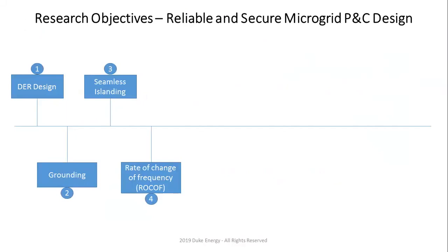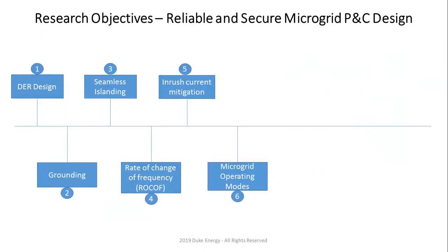Then there's going to be a section on the rate of change of frequency. I'm going to show you how we detect islanding and what elements we use inside the relay. Probably the most challenging part with the distributed energy resources that are inverter-based is inrush current mitigation. We're going to talk about that. And then once you have a microgrid, how does the microgrid operate?